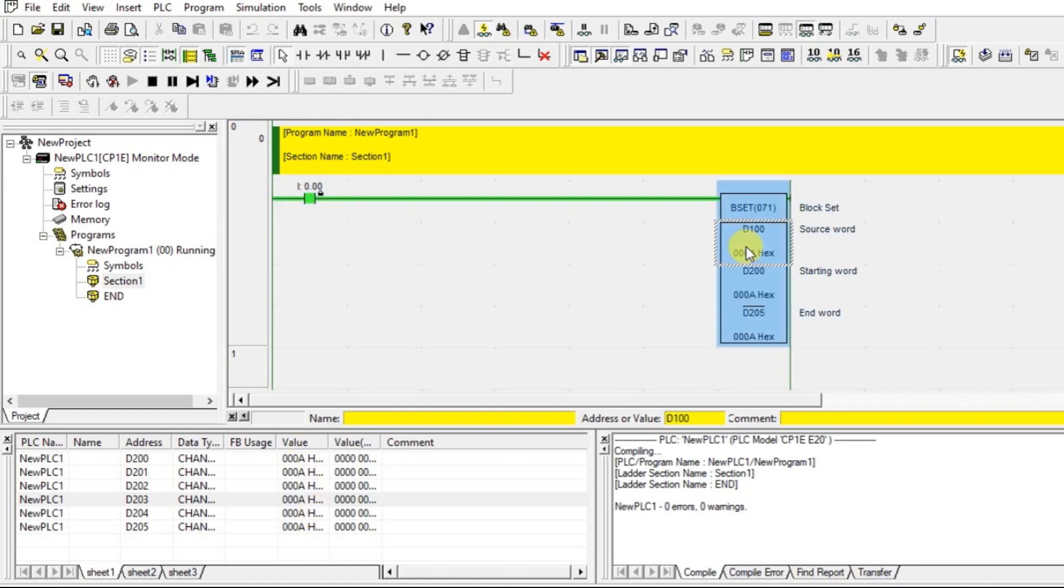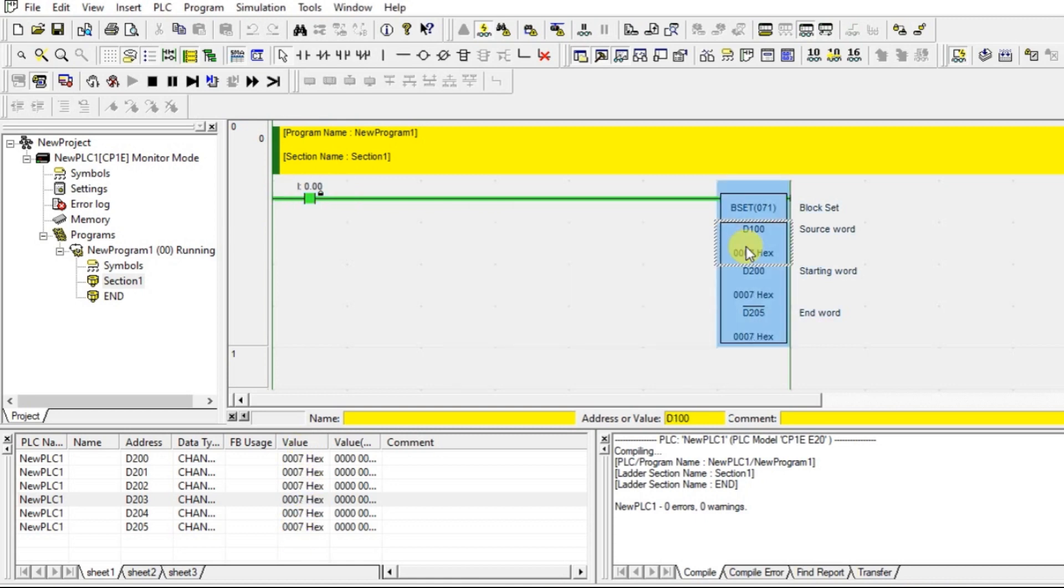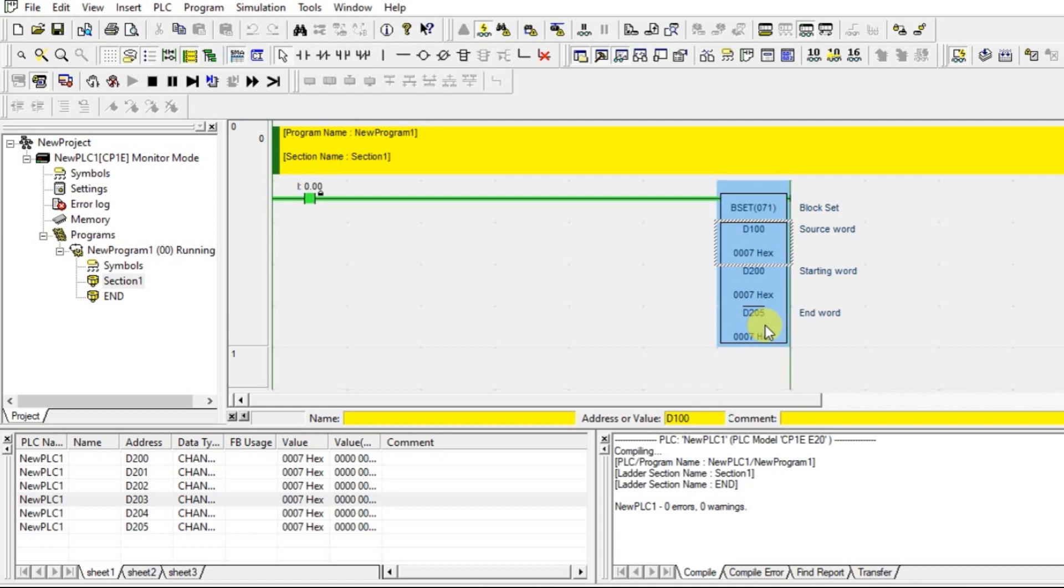Let us change the value and you can see the change in value of all those addresses. It should be the consecutive addresses. From D200 to D205 - D201, 2, 3, 4, 5 - totally in 6 places it will update. This is how block set instruction will be working in Omron PLC.